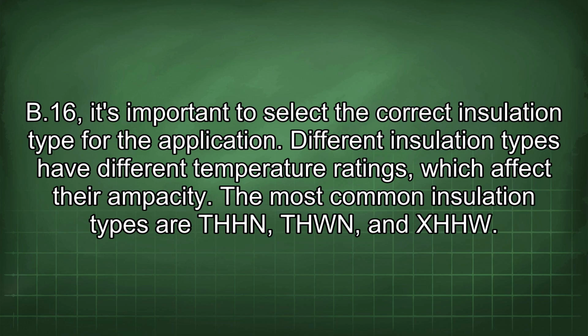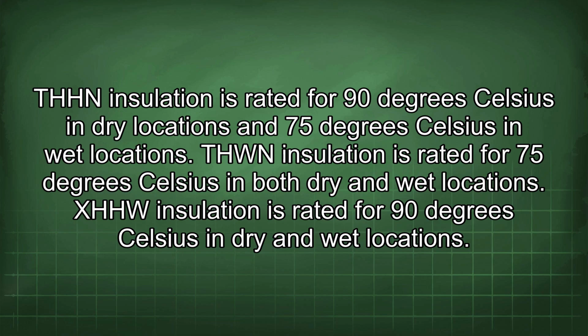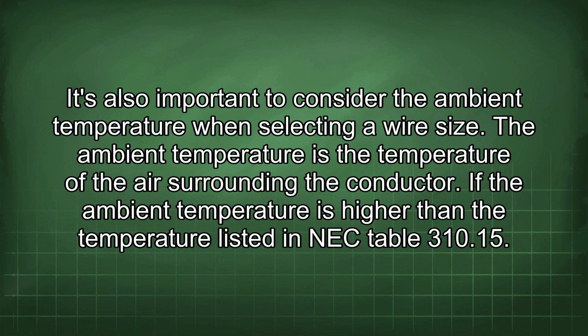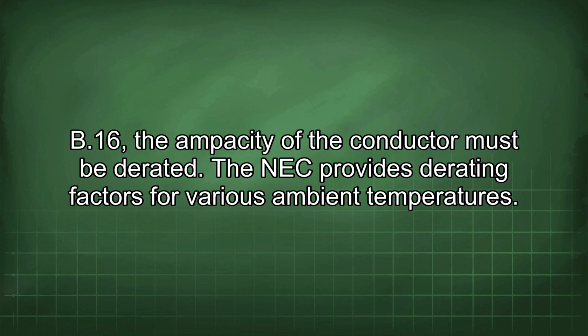The most common insulation types are THHN, THWN, and XHHW. THHN insulation is rated for 90 degrees Celsius in dry locations and 75 degrees Celsius in wet locations. THWN insulation is rated for 75 degrees Celsius in both dry and wet locations. XHHW insulation is rated for 90 degrees Celsius in dry and wet locations. It's also important to consider the ambient temperature when selecting a wire size. The ambient temperature is the temperature of the air surrounding the conductor. If the ambient temperature is higher than the temperature listed in NEC Table 310.15 B16, the ampacity of the conductor must be derated. The NEC provides derating factors for various ambient temperatures.